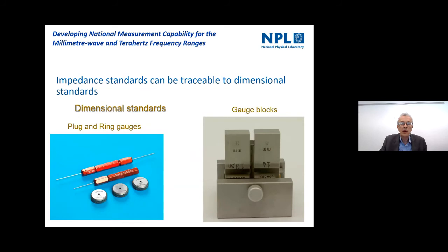We can then calibrate those air lines, the impedance standards, with respect to dimensional standards. So on the left there, we have what we call plug and ring gauges, which are basically precision rods of metal and precision holes, which we can determine and characterize against dimensional gauge blocks, which is shown on the right. So we're passing the traceability now from the network analyzer through the air lines, through the ring gauge and plug gauges, through the gauge blocks.